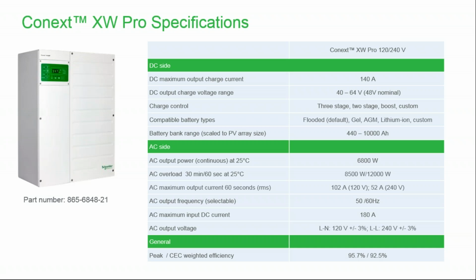The third thing that it has the capability of doing is selling power back to the grid. So if you have it set up in, say, a backup power mode where you're really not using the energy for the loads, you can sell that power that you generate from the PV back to the grid. You set it up for what battery voltage you would like it to operate at, and then it will basically sell 240 volts back to the grid at an amount of power that you set it up for.